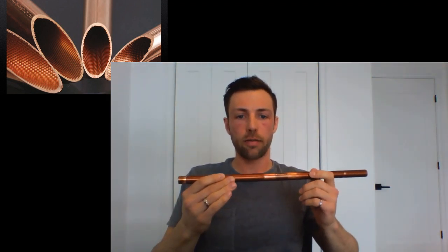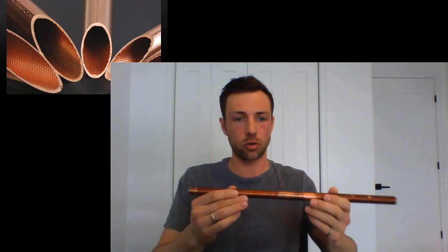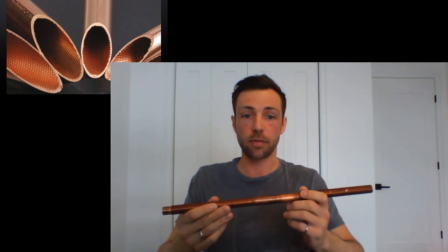And the fourth difference is that generally these tubes are very thin, thinner than what we see in normal shell and tube heat exchangers. So between 22 thousandths of an inch to 28 thousandths of an inch, and in metric, it gives about 0.56 millimeter to 0.71 millimeter. And the tubes are either 3/4 of an inch OD or 1 inch OD. So these are basically the ODs that we see, meaning it's 25 millimeter for the bigger and 19.05 millimeter for the smaller ones.